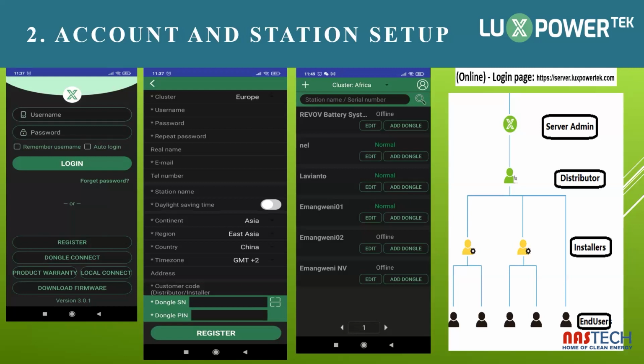There's no network access. I don't have any network on my phone. There's no Wi-Fi. So in that case, the dongle is still attached to the inverter. Will it still monitor the operation of the inverter and keep the data logs? Yes, that's correct. So for those remote areas, we can set it up where we have internet access, leave the dongle on, set the inverter up, and then if there is a fault, once I connect to the internet again, I will still have access to all the data that was recorded during the period it was offline. Yes, the data will be on the dongle. Oh, okay. So the moment it comes online again, I will then be able to download the logs. Yes, sir. That's correct.